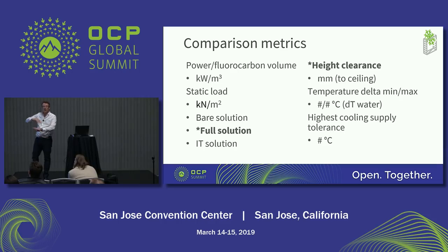With open bath, it's usually determined by the distance that you need to clear a server for extraction, right? As opposed to what some people tend to think, the lid opening, that being the maximum. No, it's actually the clearance that you need for the IT to be extracted. That's the most common height requirement. With the rack-based solution, it's simply the height of the rack.